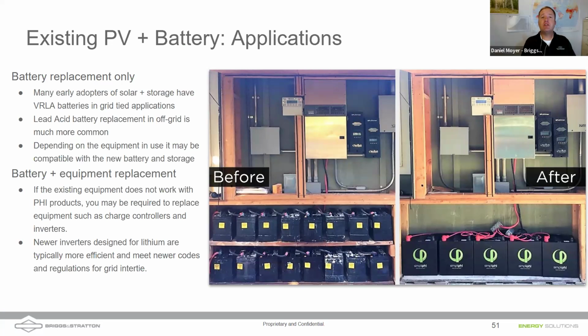That's a great concern, and I think it handles it to some extent, but it's really important - and this is a great ethos even in a grid-tied main panel - that we balance those loads. You could put a fault right on the solar; it can only handle so many amps on one of the legs. So try to balance the load center so you're feeding it evenly. Great point, it's something we should always pay closer attention to.